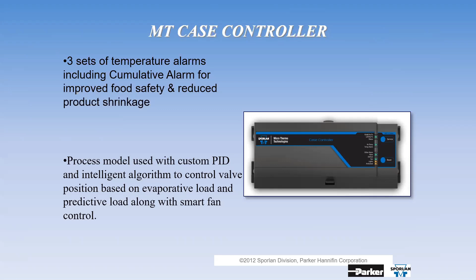Okay, so let me say that again. Temperature with superheat backup, superheat with temperature backup, pure temperature control, or pure superheat control. So we can program it either way you want it, okay? The cumulative alarms that I told you about, set 1, set 2, and cumulative, are featured in the case controller. And everything we learned from the EPR, the case type, delaying after startup, all of that. Everything we learned from the EPR, we put into the case controller.